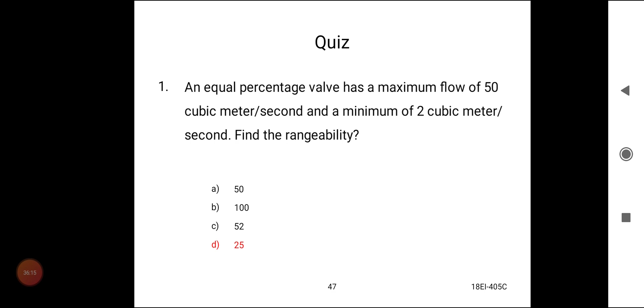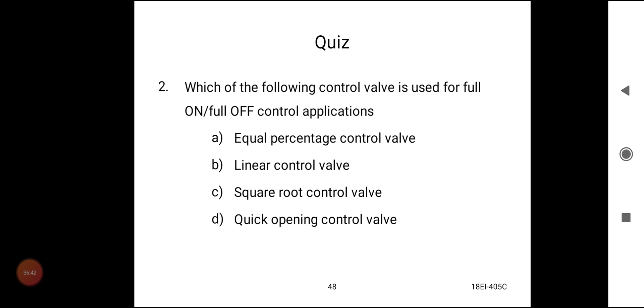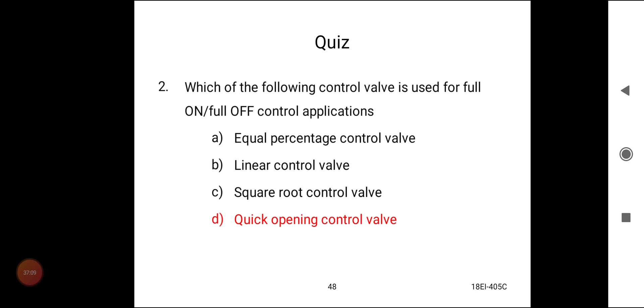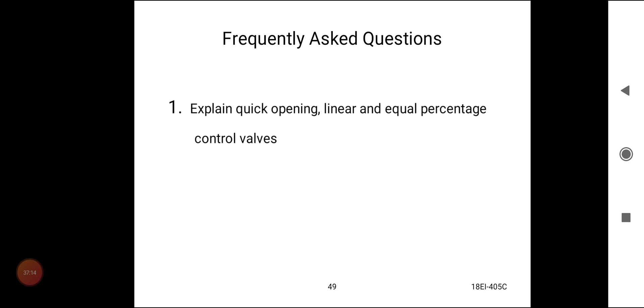Quiz second question. Which of the following control valves is used for full on, full off control applications? Equal percentage control valve, linear control valve, square root control valve, or quick opening control valve. The answer is quick opening control valve. Full on means that within 30% of the stem position, 90% of the valve will be open. Full off control is also done with a quick opening control valve. So D is correct. The frequently asked question from this topic: explain quick opening, linear and equal percentage control valves.